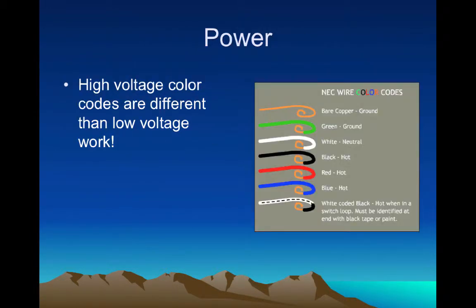It's important to note that the color coding for power is much different from our low voltage wiring. In mic cables you might see red and white and ground, or black and white and ground — it varies by manufacturer. But with power there really is a standard: black is always the hot. Red is also hot, and blue is also hot. In a three-phase system you'll see black, red, and blue as hot. In many homes, red can also be a switched hot for three-way switches. White is always neutral, and green and bare copper are always your safety ground.